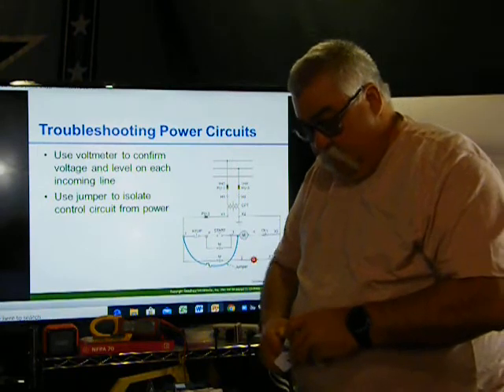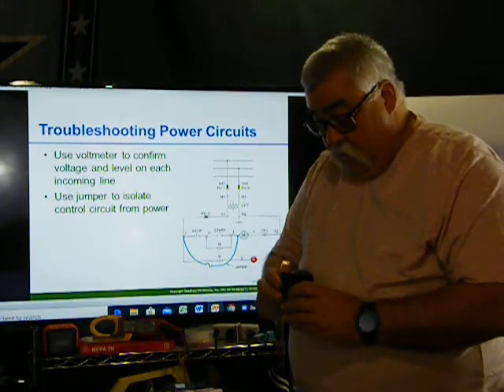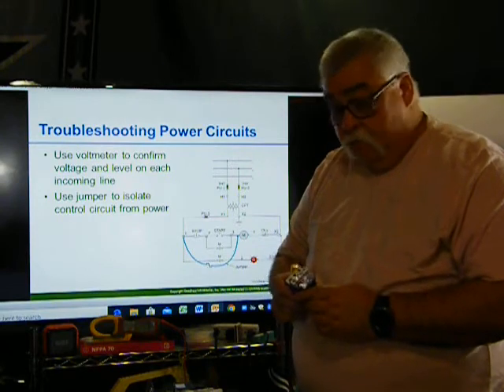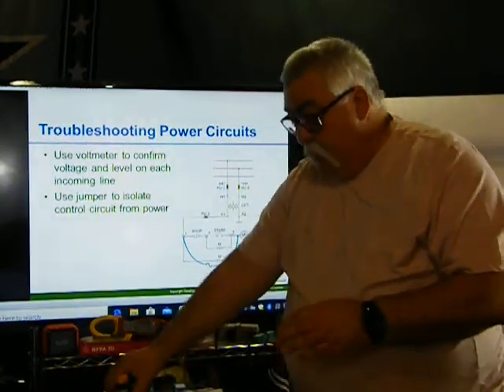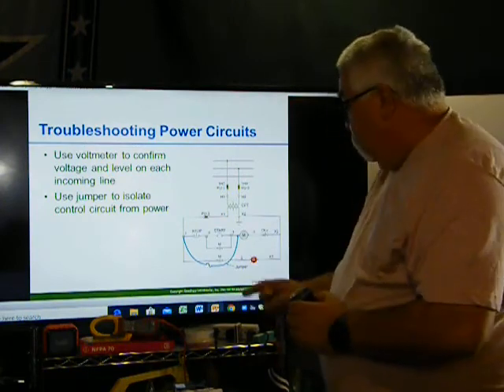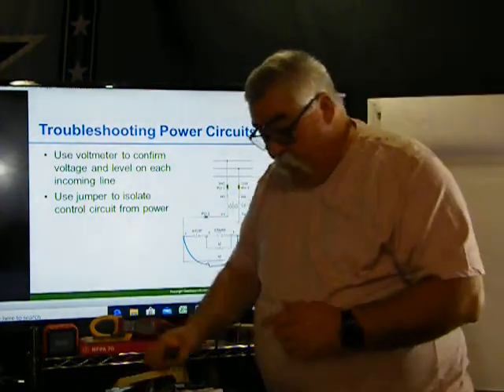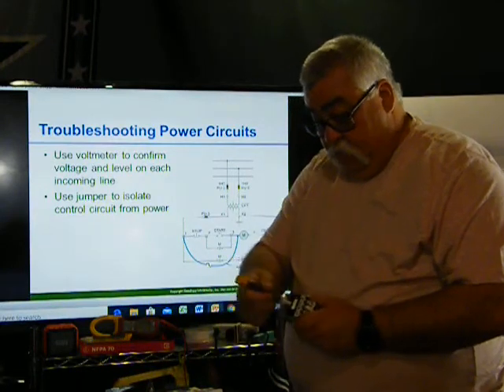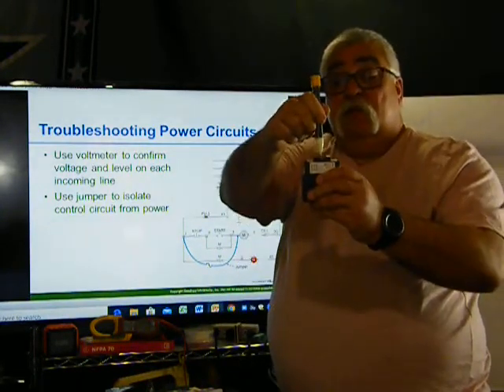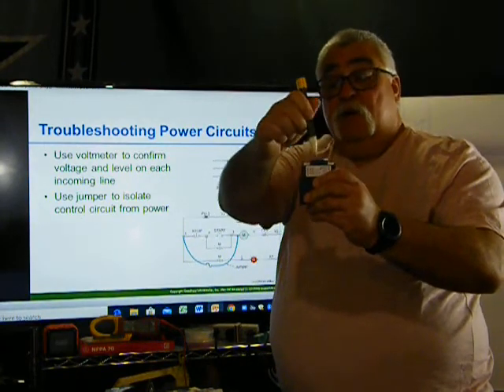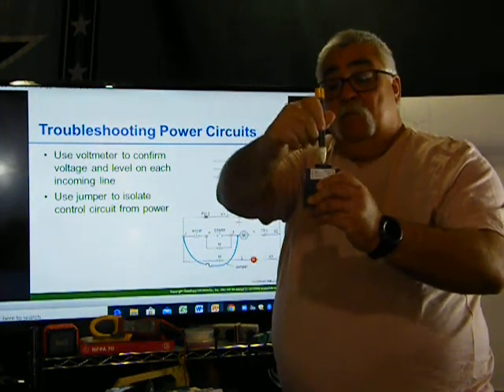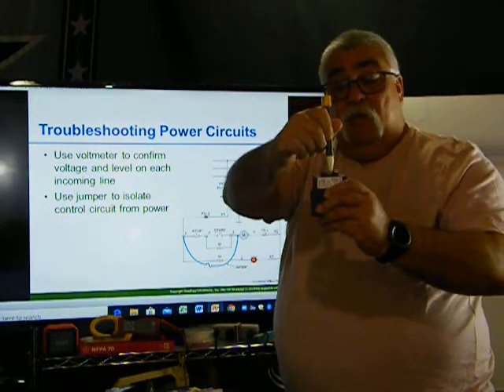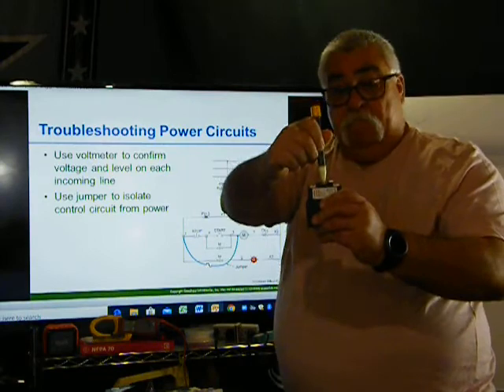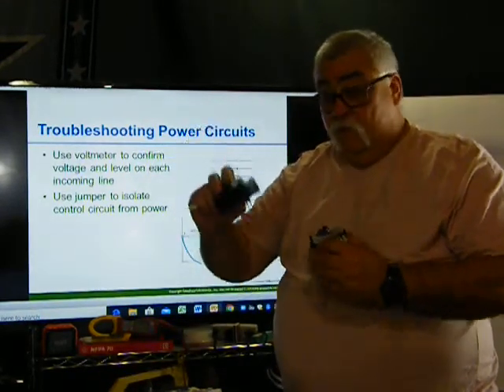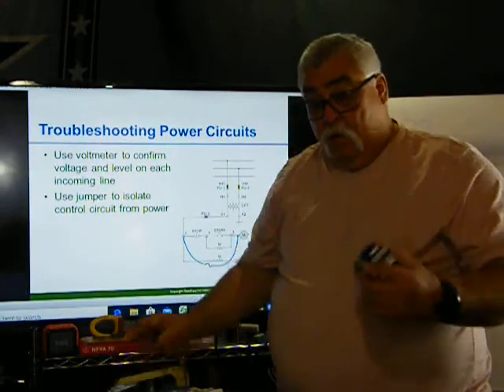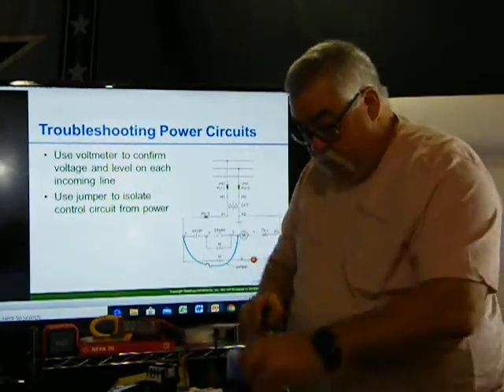Your overloads. Okay. Is my overloads causing the problem? These are all part of the controls. So we're bypassing our stop starts, I'm sorry, not the overloads, by pushing it in. And I don't know if you can see, there's this little blue part right here in the center. Pushing down. Okay, and that automatically closes, so the motor should come on. Okay, and then from there it goes straight to the overloads. Well, it might be a problem with an overload, it might be a problem with the motor, anything else.